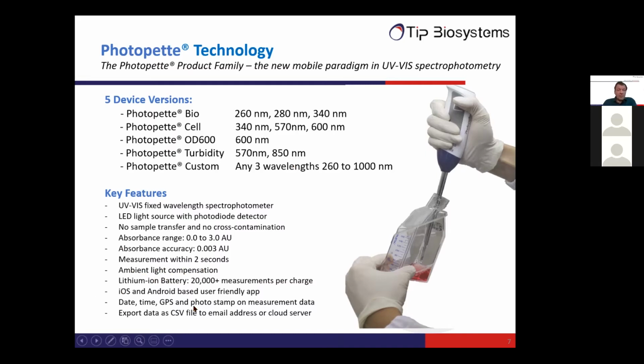The instrument is powered by a lithium-ion battery, which you do not need to charge very often. We can do at least 20,000 measurements. We tested this, and after this, we gave up testing. So this is really sufficient. We have software for iOS and Android. I will come back to the software later. It's very easy and user-friendly. With the data of your absorbance or transmission, we also save the date, the time, and the GPS position. And you can even take a picture or write a note. All this data is exported as a CSV file, and you can send it to your email or you can upload it to a server.